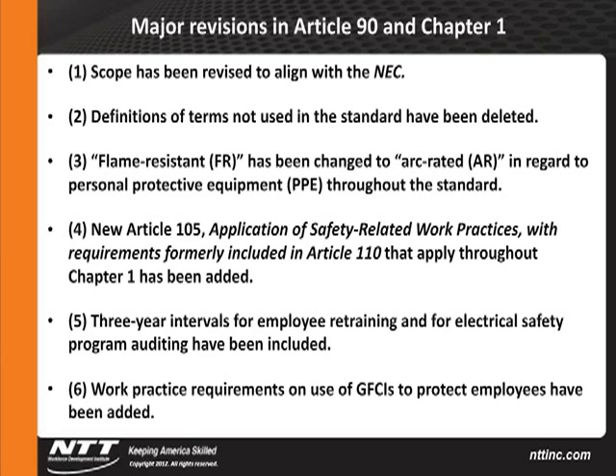They've added a significant change for many of you out there. FR, or flame-resistant clothing, has been used in the past. Well, they've changed that to arc-rated clothing. Why? Because many companies are using FR clothing, but it's not what it's designed to be used for. Article 105 is new. One of the other significant changes we'll get into is a 3-year interval for retraining and auditing of your programs. Another one is the workplace requirements for GFCIs. It's been in the NEC. It's being reinforced again in the NFPA 70E.